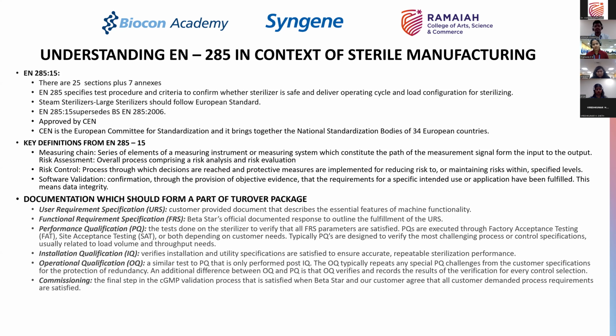You will check whether all the components which were shipped from the factory are correctly installed, they are correctly labeled, the insulation is done for all the hot lines, etc. So that is what falls under installation qualification.